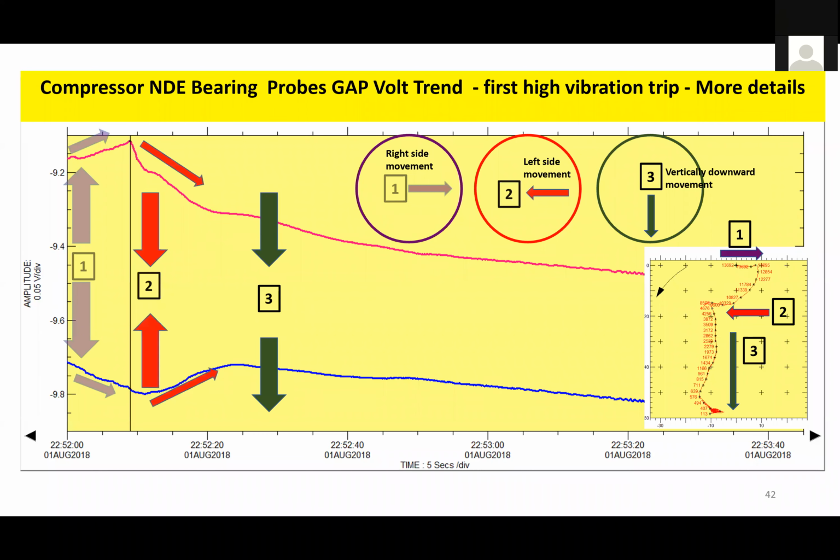And also when a rub is happening, when an instability is happening, when shaft cracks are happening, you need to understand these plots also, how these plots help us visualize those events. So a really good diagnostic person will try to compile all this information and not draw a conclusion from looking at one or two plots. Sometimes the problem could definitely be identified by looking at one or two plots, but it is always better to see the other plots also and see whether they are saying the same information or giving a different picture. So that will definitely add value to your diagnosis.